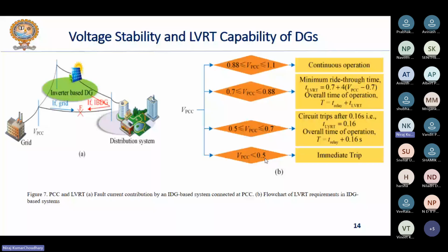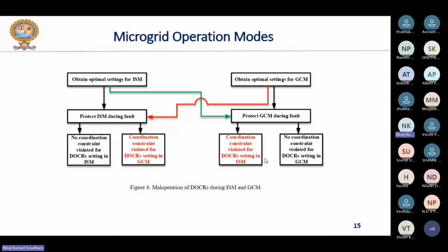Now, after discussing the challenges associated with the voltage stability and transient stability condition, another challenge faced by the protection coordination schemes is due to the change in mode of operation of the microgrid. That is the transition in the operation mode of microgrid from grid connected to islanded mode. Now, what will be the problem in this condition? Suppose your system is operating in the islanded mode of operation, then the objective of any utility is to protect the system during faulty condition in that particular mode of operation, right? So accordingly, you will calculate the relay settings depending upon the fault current in the system, right?